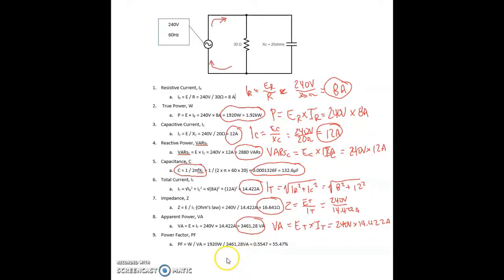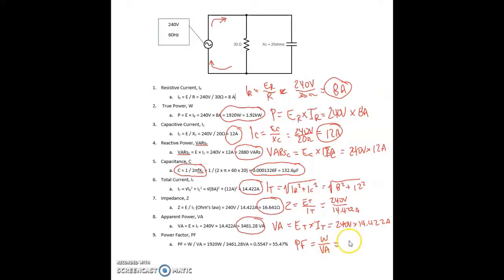And for power factor, we're using the same formula: power factor equals true power in watts over apparent power in volt-amps. Power factor equals 1,920 watts divided by 3,461.28 volt-amps, which equals 0.5547. Power factor is typically given as a percentage, so that's 55.47%.